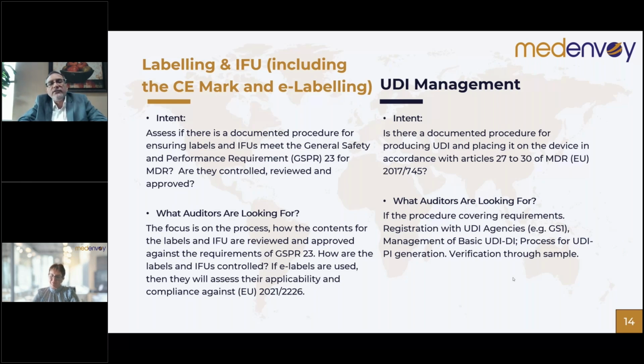So procedurize elements, and how do we maintain and capture all the requirements from GSPR 23 into your process procedures, and then as a sample, we will take a version of a label and then follow through these elements.